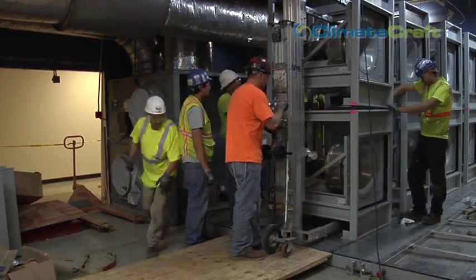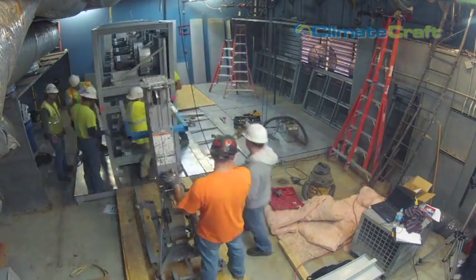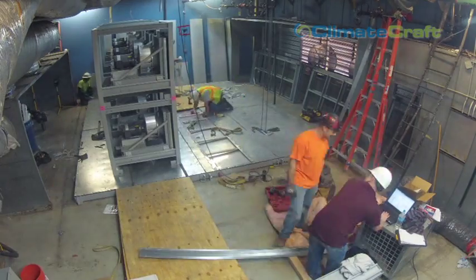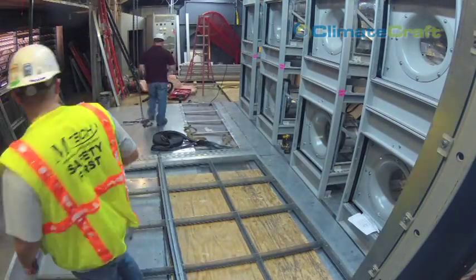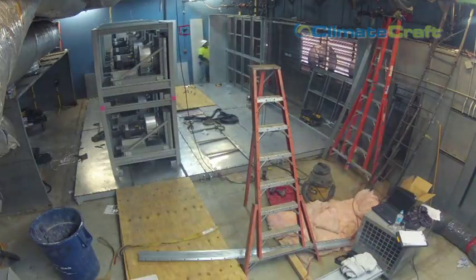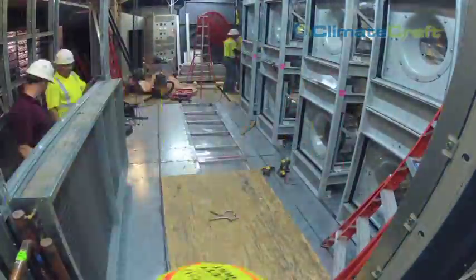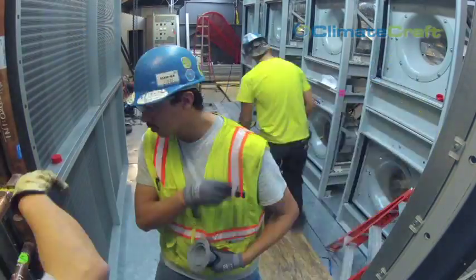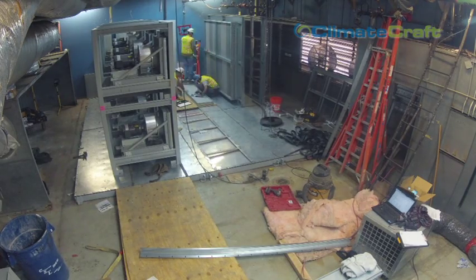Access is more than just a knockdown air handling unit. ClimateCraft access units deliver lower operational cost via ClimateCraft's unique fan array design, permitting easier maintenance. The direct-drive plenum fans are quieter and have no belts or sheave efficiency losses. With other air handling units that run one or two large horsepower fans, a possible fan failure is a much greater issue as there is no way to compensate for the lost airflow. It appears that things will be easier to maintain — if we have an issue with one of the fans, we can take one of the eight fans out. We could also shut down one of the VFDs if we have a problem, because there are two that feed it. With the old unit we had to shut down the whole fan if we had an issue, whereas here we don't have to do that.